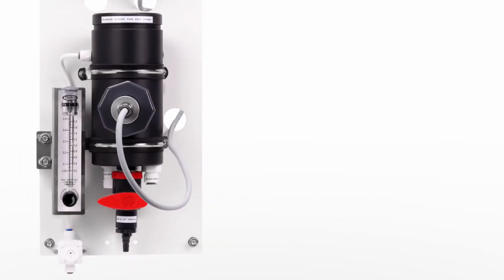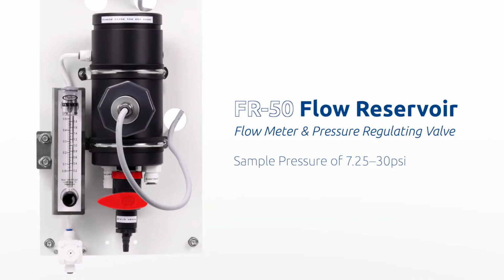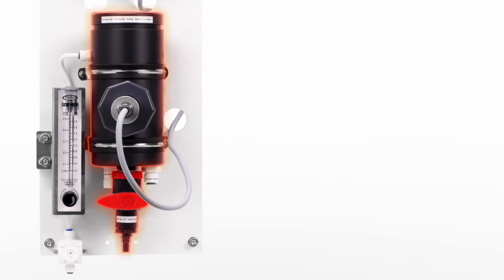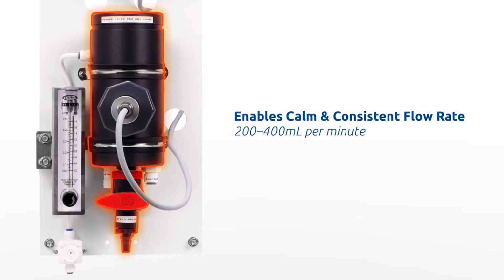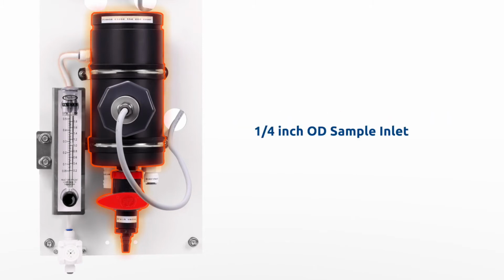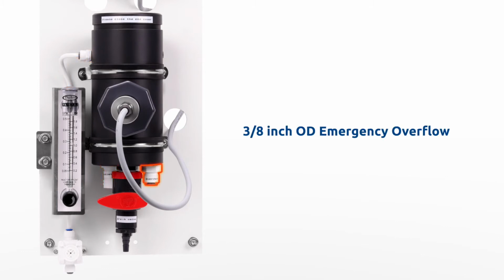Each sensor is provided with the Pyxis FR50 flow reservoir, flow meter, and pressure regulating valve. Capable of being operated on sample pressures ranging from 7.25 to 30 psi, this uniquely designed flow reservoir serves as a flow and pressure regulating vessel, enabling a calm and consistent sample flow rate of 200 to 400 milliliters per minute across the reference electrode assembly for optimal performance. The reservoir provides a 1/4-inch OD sample inlet, 20mm sample outlet, 3/8-inch OD emergency overflow, and 1/2-inch NPT drain valve, as well as a quick adapter for rapid sensor removal and maintenance.